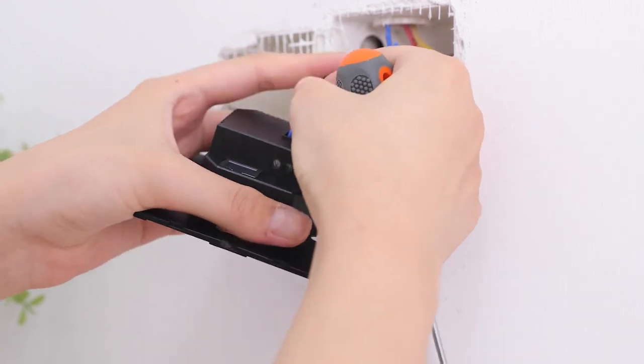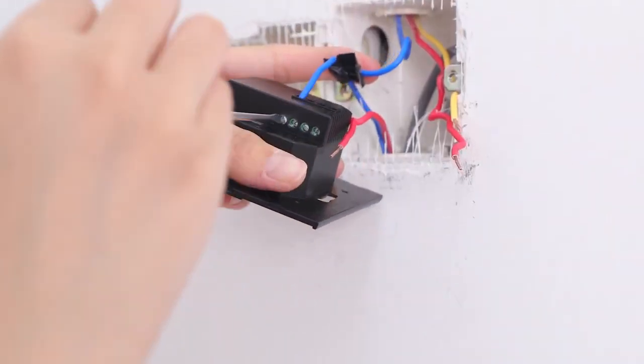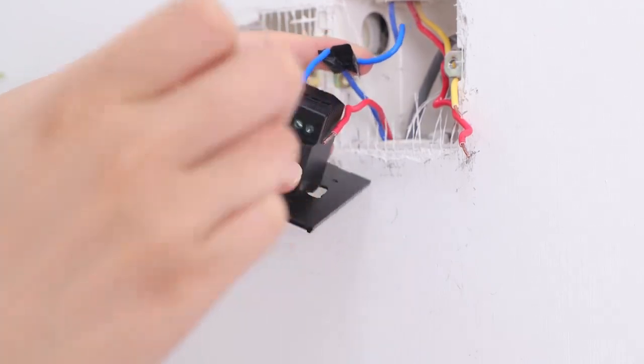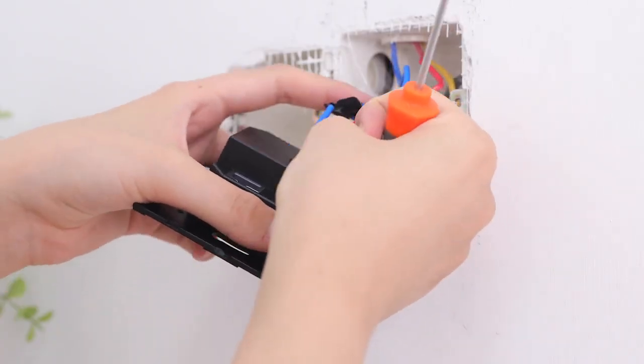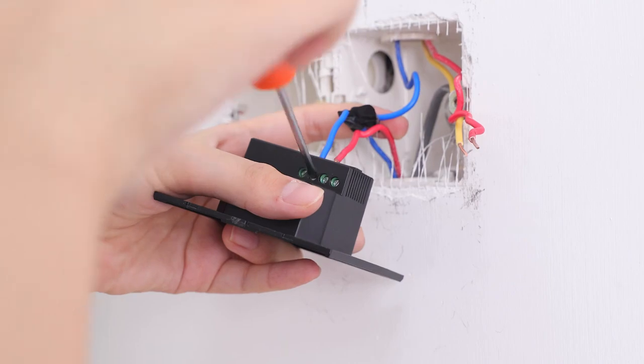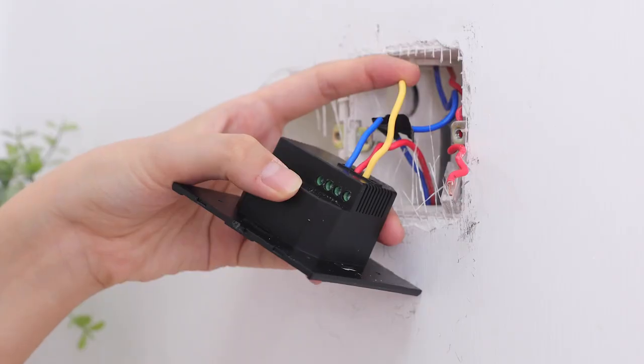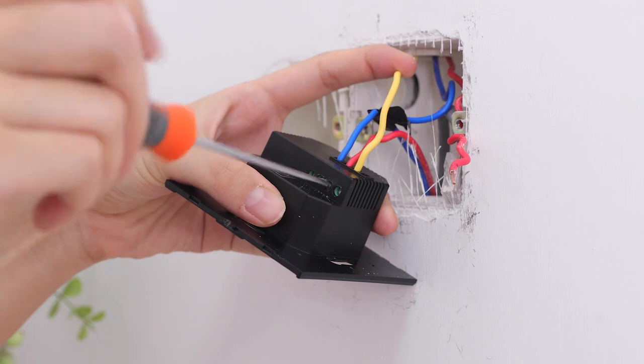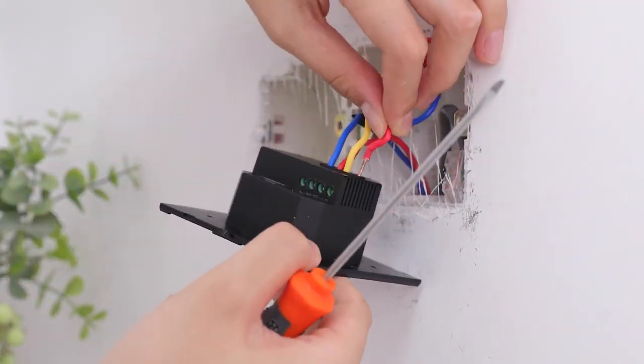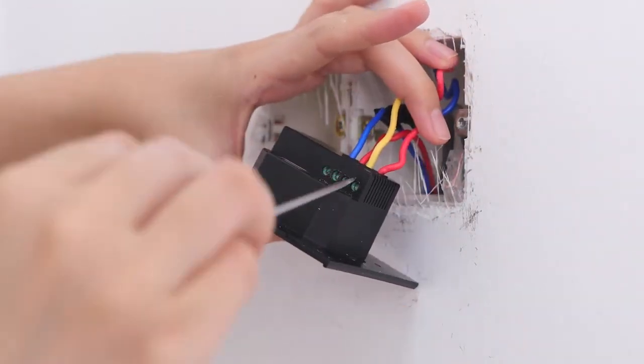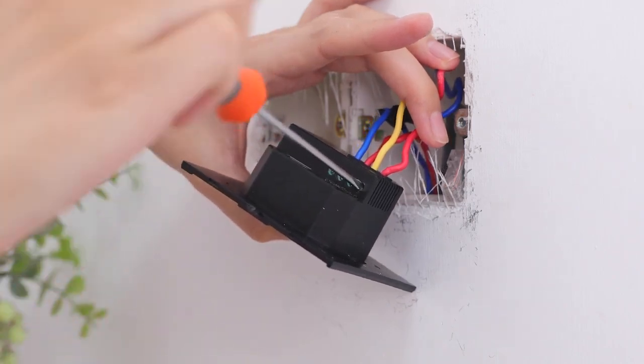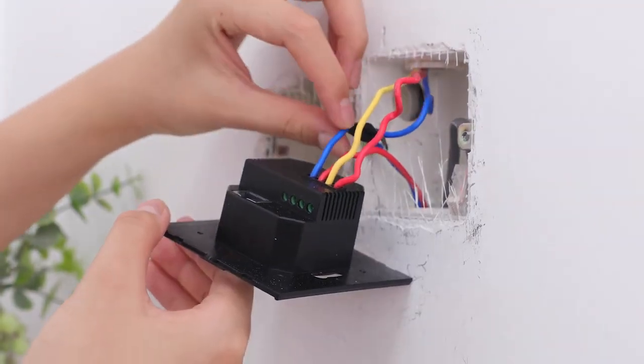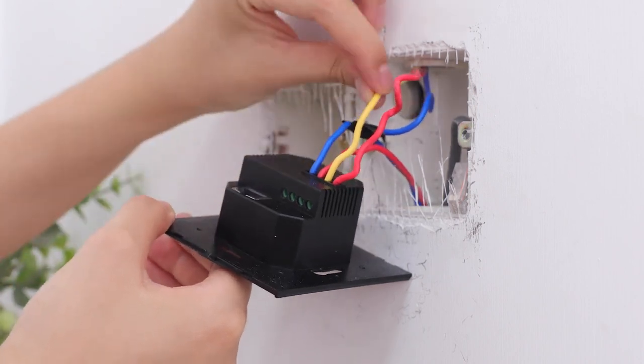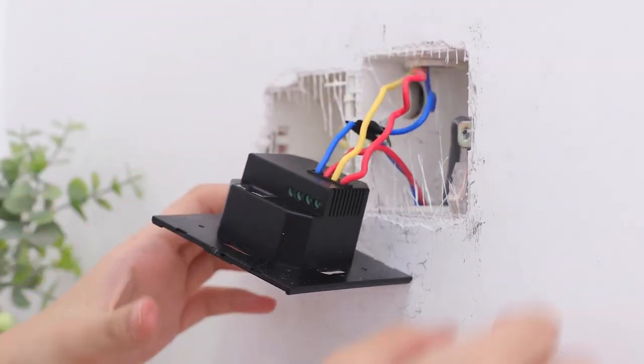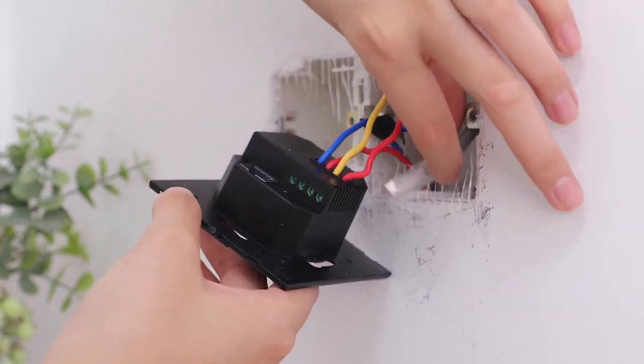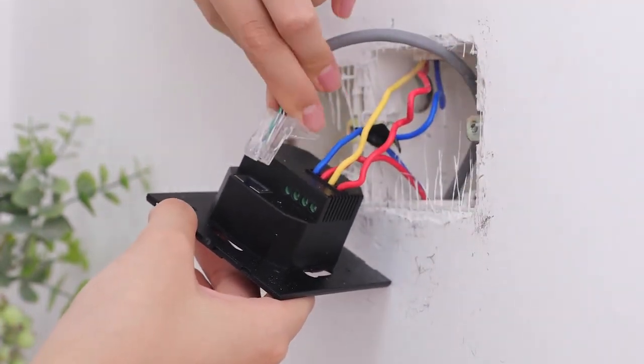We'll start by inserting the neutral wire into the N terminal and tighten the screw. Now screw the red line wires in the L terminal, and load wires into L1 and L2. Check all the wires are in the proper place and secure. Test by tugging. Plug the RJ45 network cable to the Ethernet port if you need to use the wired network.